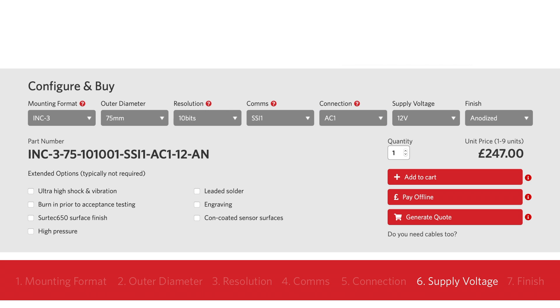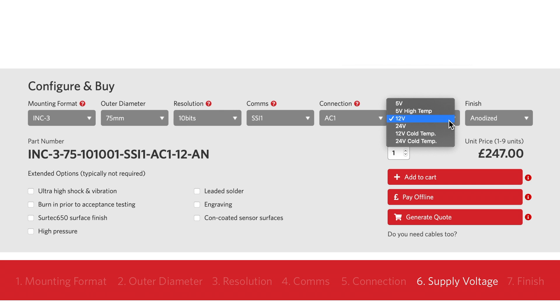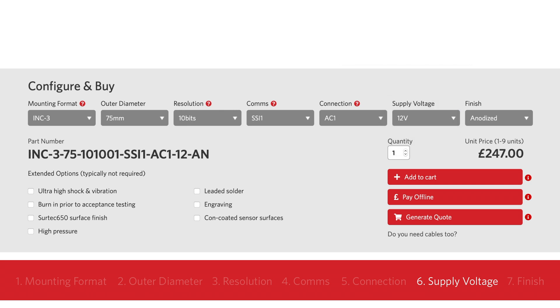The next element is supply voltage. For operating environments with temperatures up to 105°C, select the 5HT option. For low temperature applications down to minus 60, choose the 12CT or 24CT options. For analog voltage output you'll need a 12 or 24 volt supply. In this example we'll choose the most common supply, 12 volts, which covers a range of 4.5 to 32 volt DC.